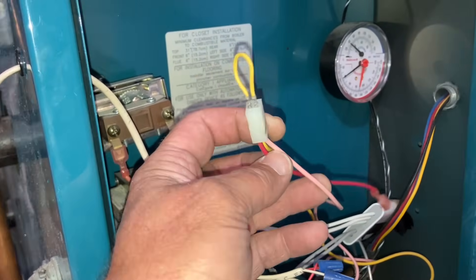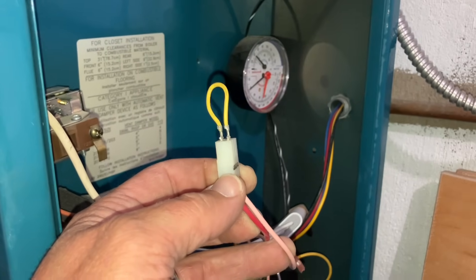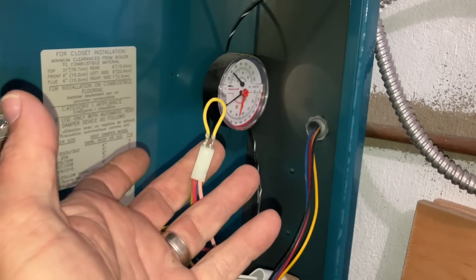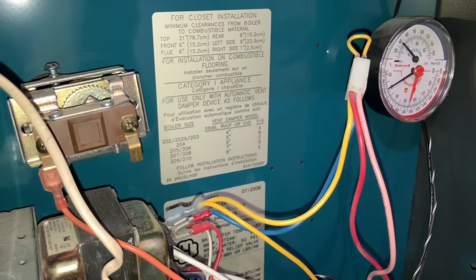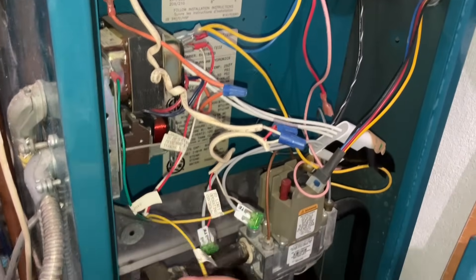Beautiful. I didn't notice this before, but your automatic vent damper has been bypassed with a little wire. Here's your vent damper, and this is what someone did. Wow! You can't make this stuff up. This is the first real epic fail of the heating season of 2025–2026 and we haven't even started yet. I noticed this when I went to wire in the low water cutoff — I removed the red wire from the high temperature limit to splice them together and then I noticed this.